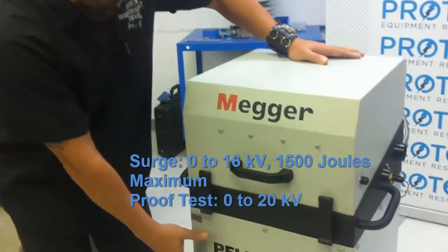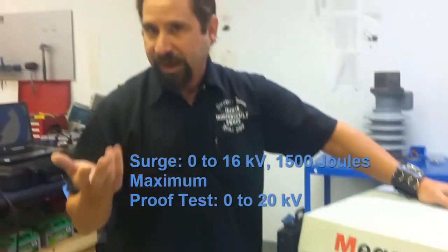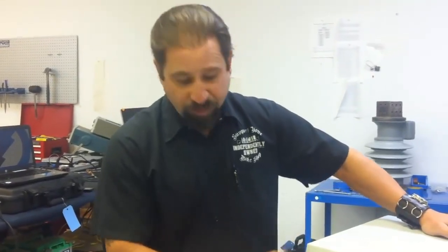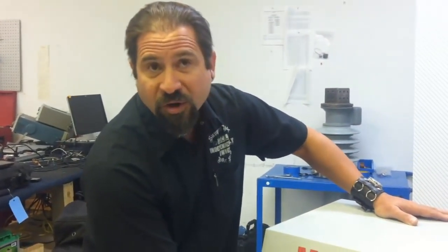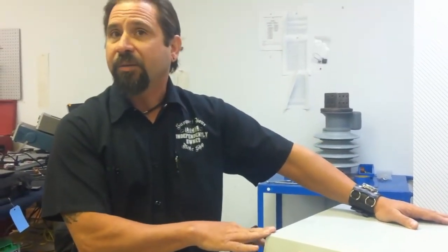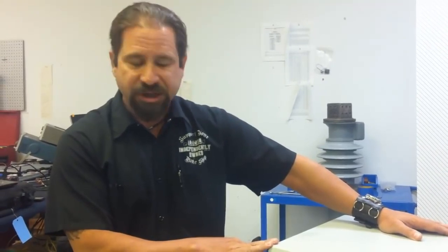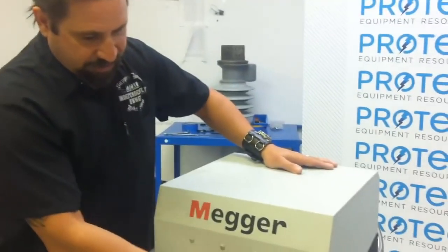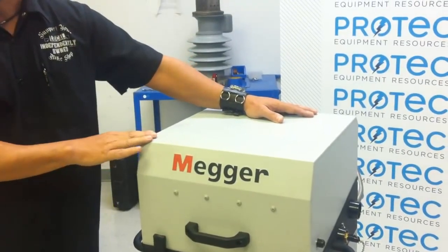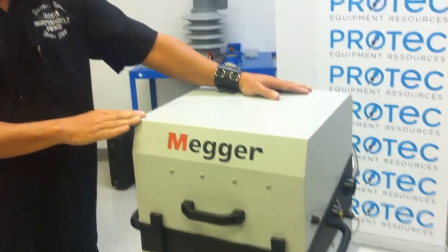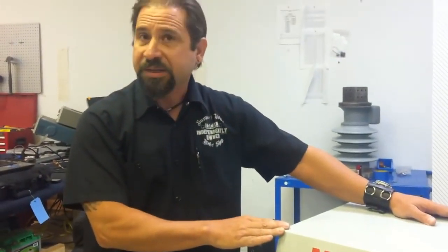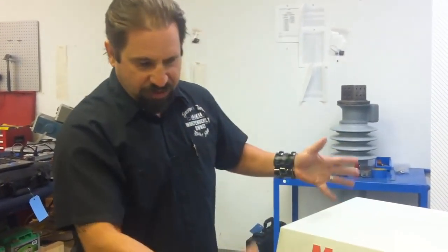Also housed within the same unit are your arc reflection or cable radar based coupling devices, which will support the arc reflection, the pulse echo, and impulse current techniques of time domain reflectometry. So all of that coupling is in the lower section, along with all of your high voltage thumping and proof burn testing capabilities. The top unit, which has a flip-up lid, houses the actual circuitry for the time domain reflectometer system. So again, it is all self-contained.